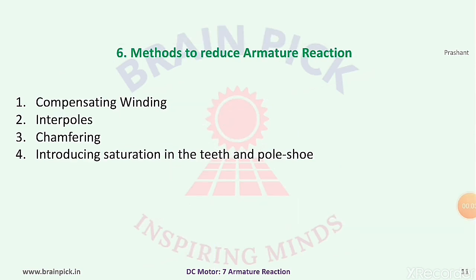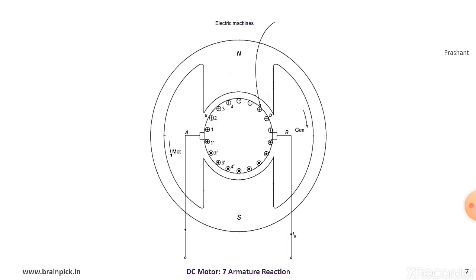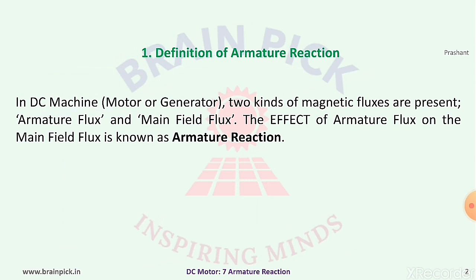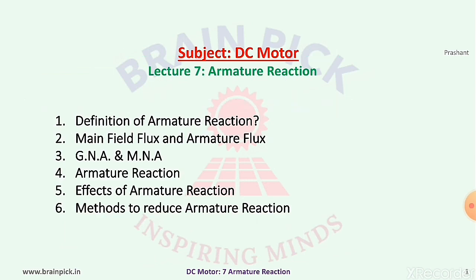Methods to reduce armature reaction: armature reaction can be reduced by number one, using compensating winding; number two, using interpoles; number three, chamfering; and number four, introducing saturation in the teeth and pole shoe. This is the end of lecture number seven on armature reaction. The armature reaction in a DC motor or DC generator is the same — the only difference is the shifting of MNA.